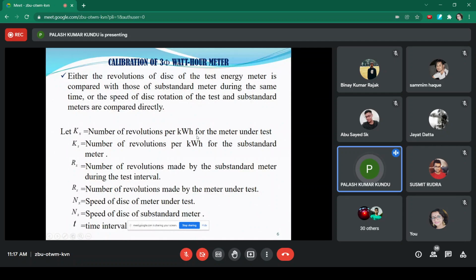Let Kx be the number of revolutions per kilowatt hour for the meter under test. Ks is the number of revolutions per kilowatt hour of the substandard meter. Rs is the number of revolutions made by the substandard meter during the test interval.